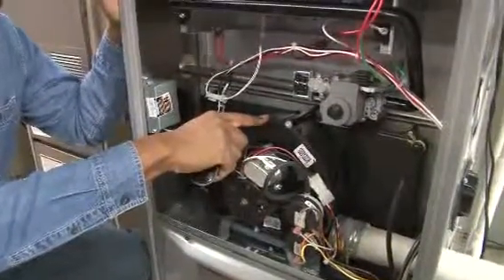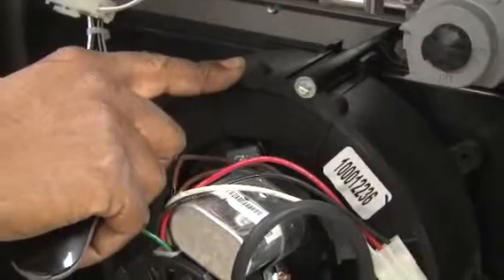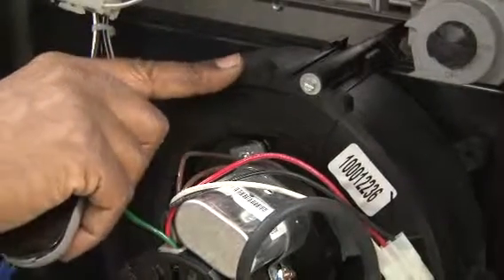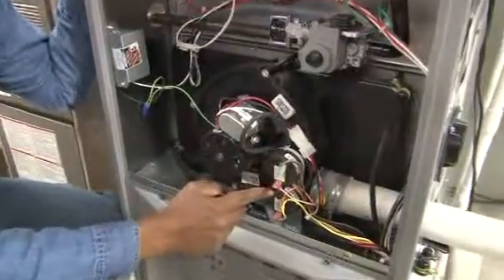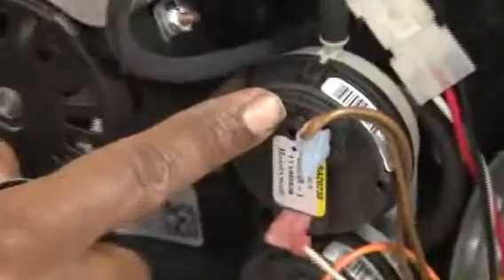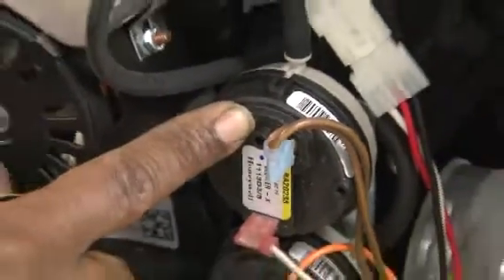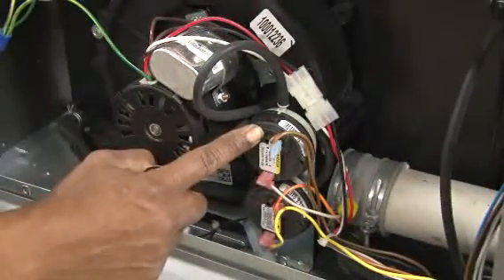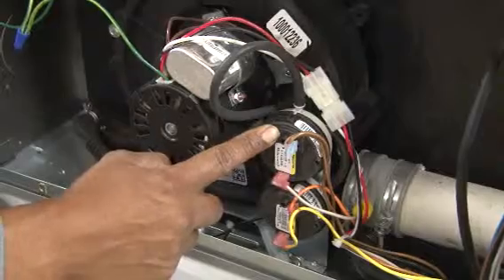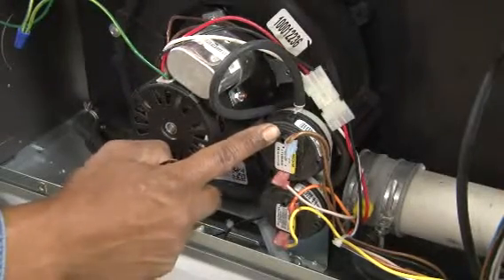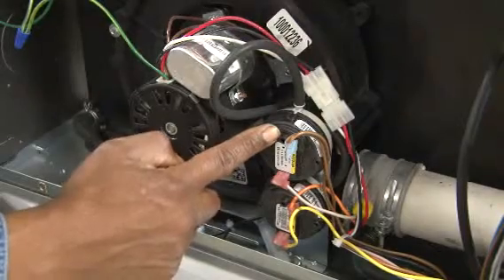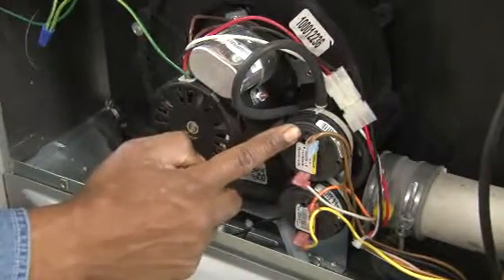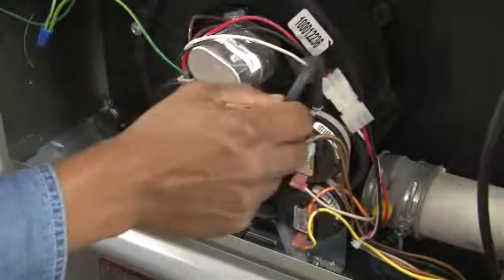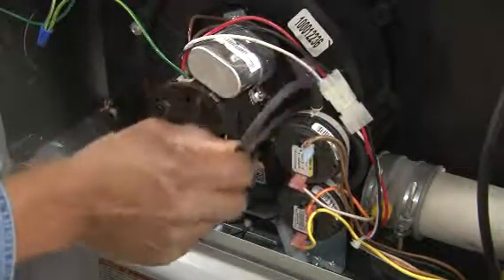This is the motor, and inside of this blower housing is a blower wheel, which will cause the movement of flue gases. Also part of this is safety. There are safeties, which are our pressure switches, to allow the system to sense that there's airflow of the flue gases through the combustion chamber. The problem is, if there was no type of safety, it can cause a problem if the blower didn't operate, and cause the flame to overheat the furnace and cause destruction. So this is actually sensing movement of airflow through the combustion chamber.